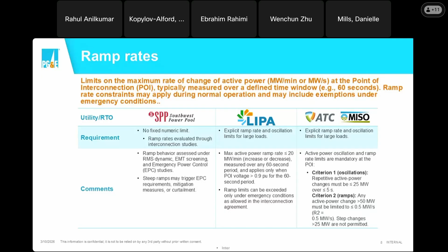Right, and if you look at LIPA as well, they have a similar 20 megawatt per minute requirement, and that has a 60-second period. While this presentation says that for ERCOT, there is no requirement, I think about 2 weeks back, it was actually presented at one of the ERCOT working groups. They are thinking about a 10 megawatt sliding window requirement over 5 seconds. And there is some feedback as well on how they arrived at those numbers. It seems to be derived by a combination of mostly forced oscillation induction into the system, while also taking into consideration the impact on area control error. If we can move to the next slide, please.